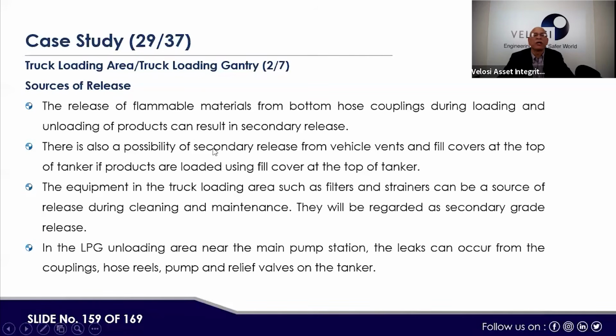There is also the possibility of secondary release from the vehicle vent and fill cover at the top of the tanker if products are loaded using the fill cover at the top of the tanker. The equipment in the truck loading area, such as filters and strainers, can be a source of release during cleaning and maintenance. They will be regarded as secondary grade release. In the LPG unloading area, near the main pump station, the leak can occur from the couplings, hose reels, pump and relief valves on the tanker.